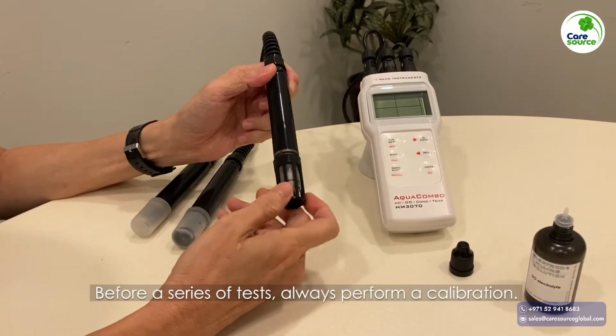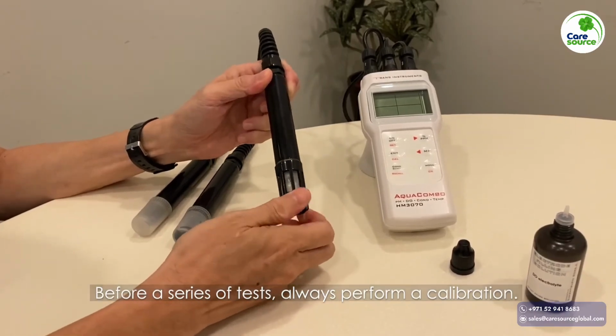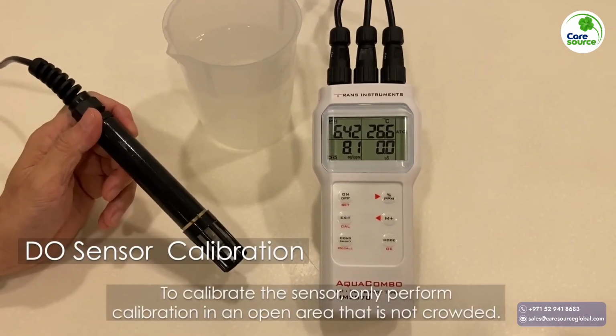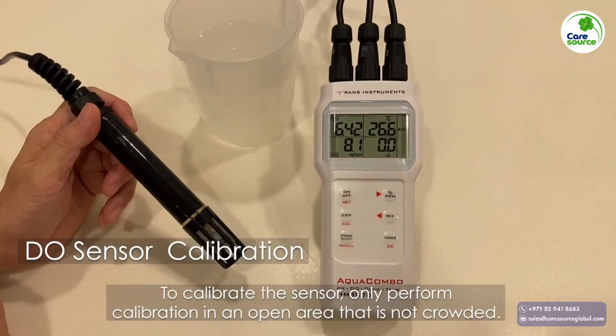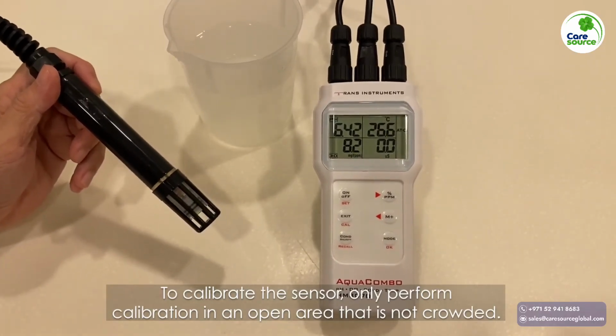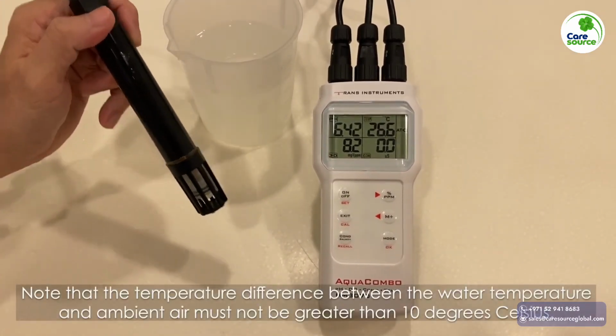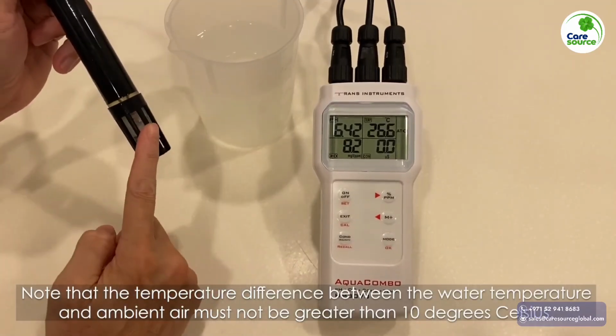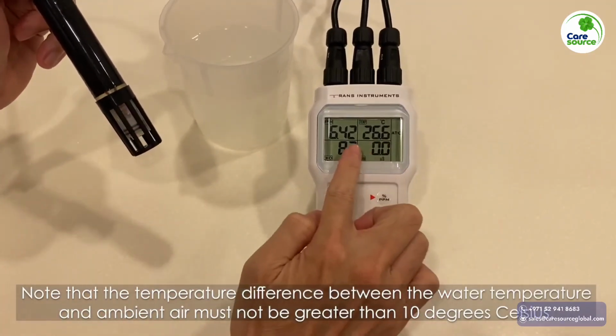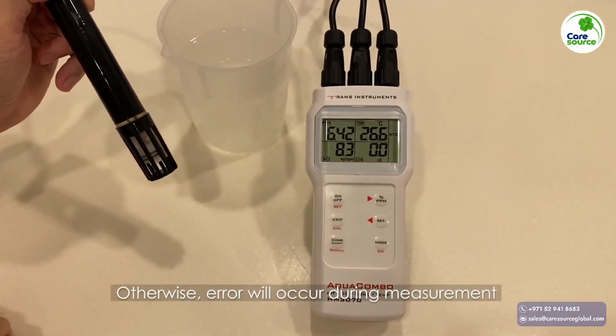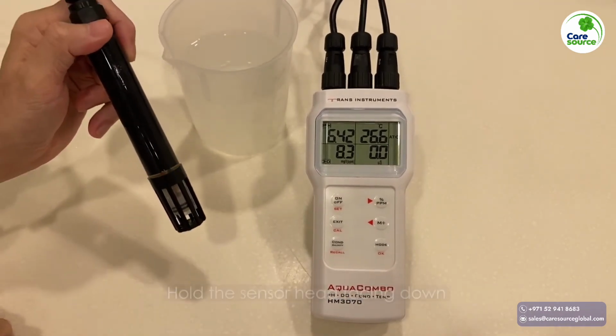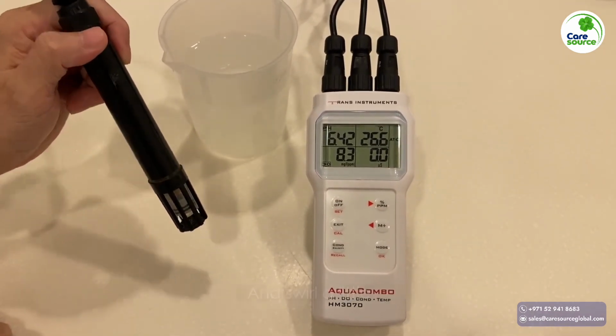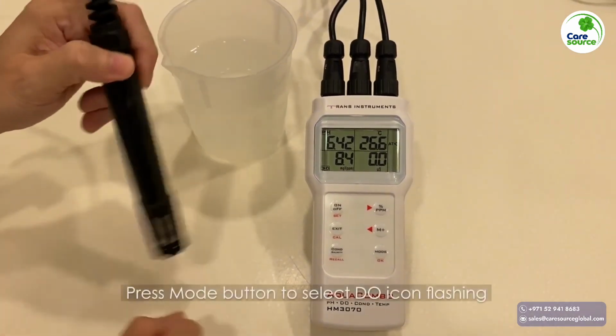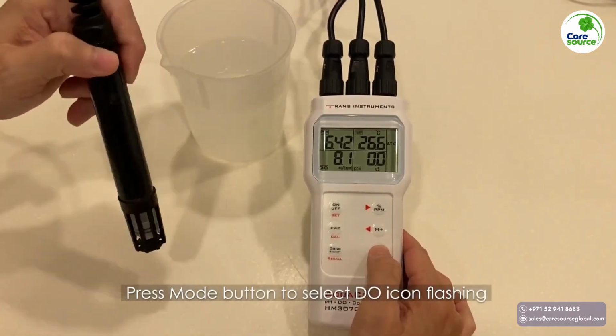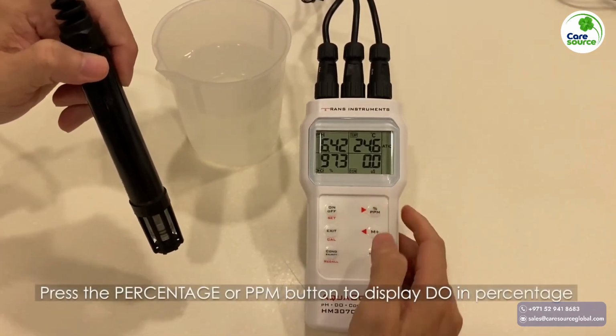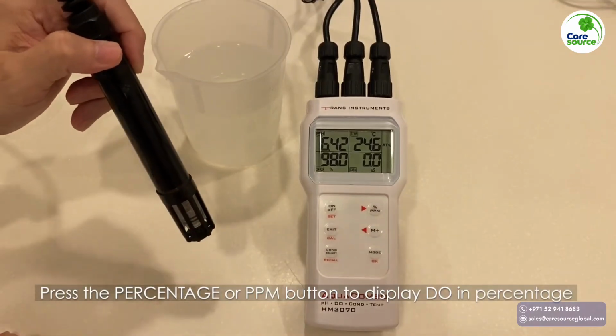Before a series of tests, always perform a calibration. To calibrate the sensor, only perform calibration in an open area that is not crowded. Note that the temperature difference between the water temperature and ambient air must not be greater than 10 degrees Celsius, otherwise an error will occur during the measurement. Hold the sensor head facing down and swirl a little. Press the Mode button to select the DO icon flashing. Press the percentage or ppm button to display DO in percentage.